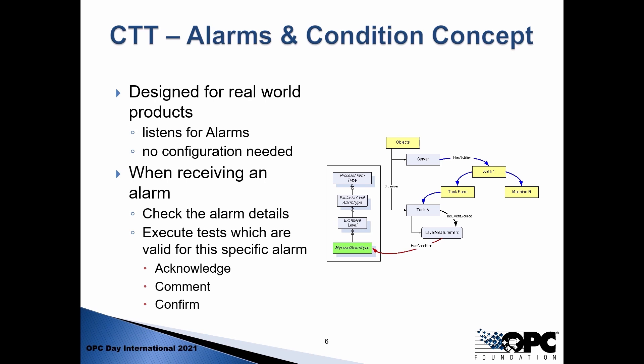The way we are testing alarms is slightly different than other tests. Those test cases and scripts are designed for real-world products, so we don't expect to write values to trigger alarms — because for a temperature sensor it is unlikely that we can actually write to the temperature value. The beauty of that is because we're just listening for alarms, there's no configuration needed, at least not for the conformance units currently shipped. There will be some minor configuration needed for the following set. The way it works is we basically listen for an alarm and once we receive it, we check whether all the alarm detail fields are present that we are looking for.